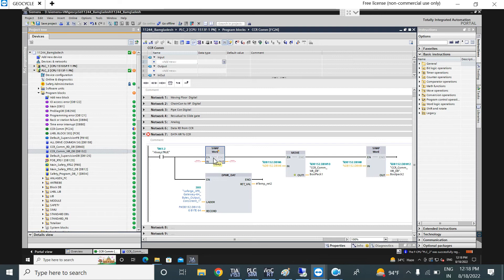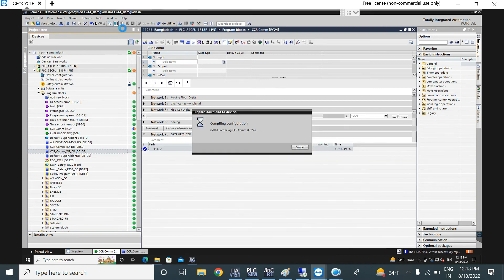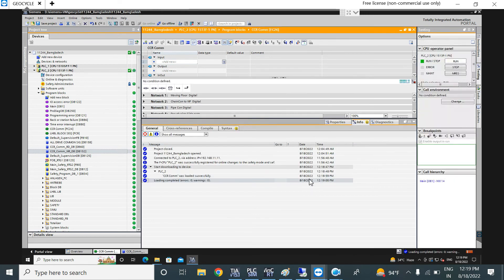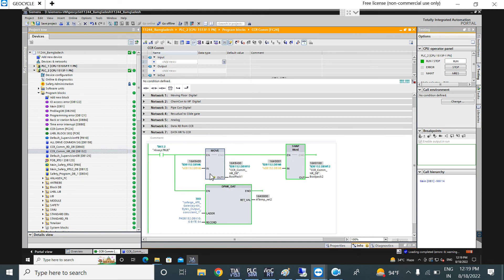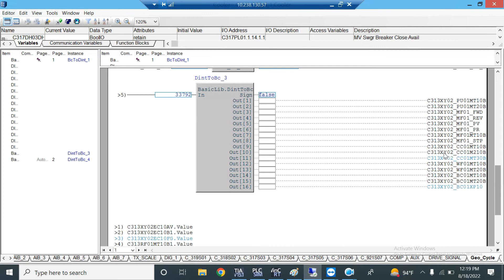Now I am sending data without swapping — just moving the data directly without the SWAP instruction. I will download this to the PLC. In the byte input and output there is no change now. Looking at the ABB PLC, you can see the byte is swapped — what was in bits 1 to 8 is now in bits 9 to 16. Out 3 is now in position 11, and out 8 is now in out 16.